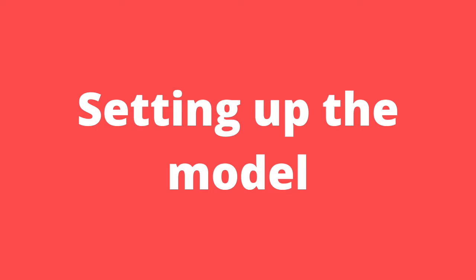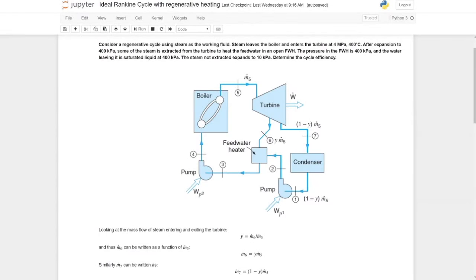Let's consider the problem. On your screen you will see a diagram of the Rankine cycle and we have added a feed water heater. Essentially, steam is bled from the turbine and is added to the feed water, heating up the water as it gets pumped to the boiler. The benefit is that the water gets preheated so the boiler does not need to heat it up all the way from condenser temperature, meaning the heating required is less significant and your thermal efficiency will benefit.